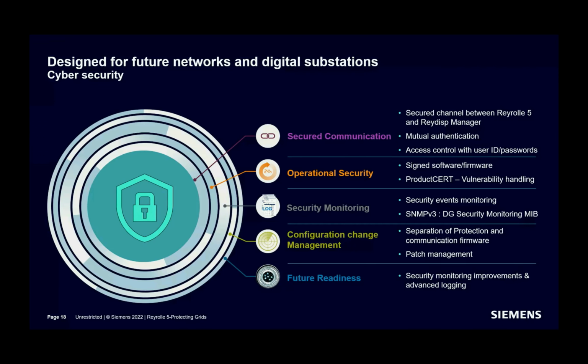The 7SR5 device provides user authentication using a connection password and maintenance password. Those passwords conform to the cybersecurity requirements for assigning passwords defined in NERC-CIP. Protection firmware and communication firmware are also separated for a more secure firmware management.